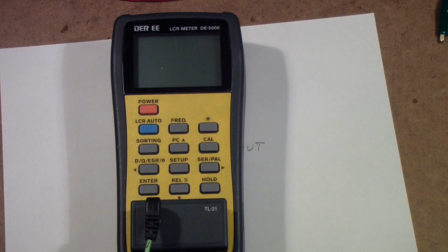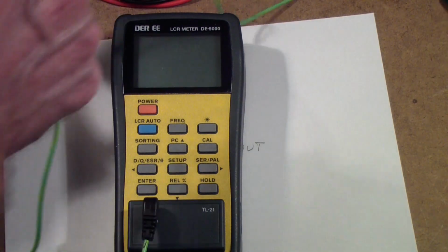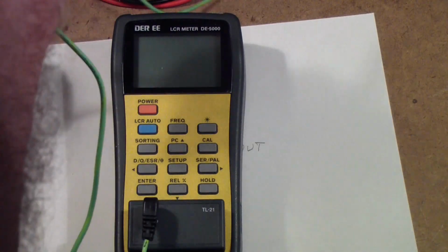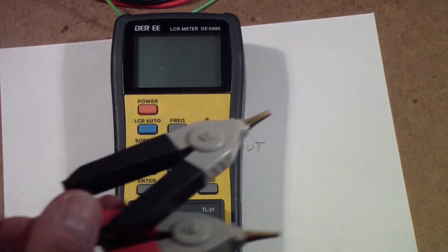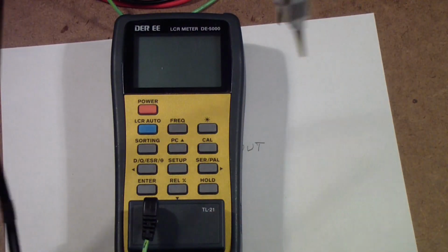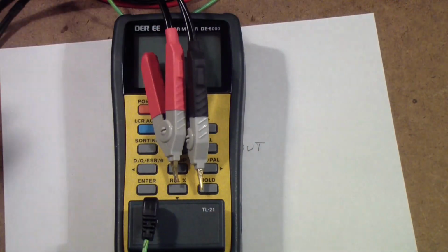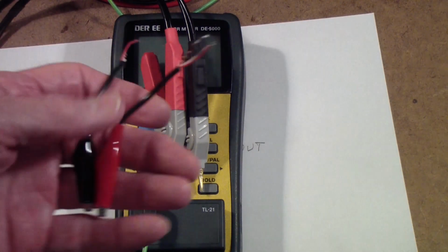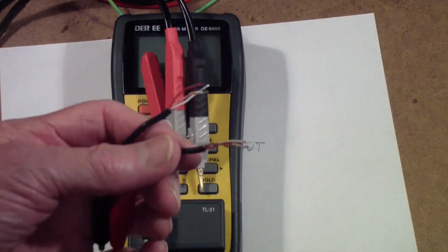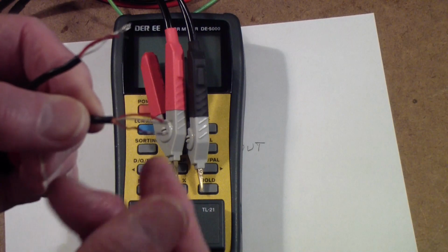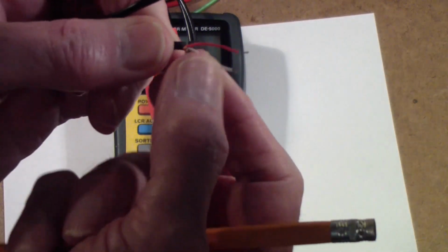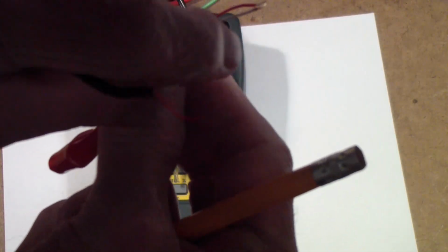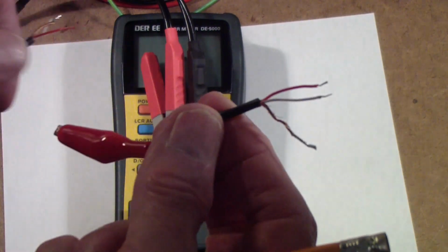But more important than anything else, if you want accurate readings with a meter like this, you have to have Kelvin probes. Now, these are Kelvin probes that I added to this meter. It comes with a pair of alligator clips. You may or may not be able to see, but there actually are 3 wires for each clip - 2 wires per clip plus a ground, or what's in metrology often called the guard. So this is a 4-wire system.